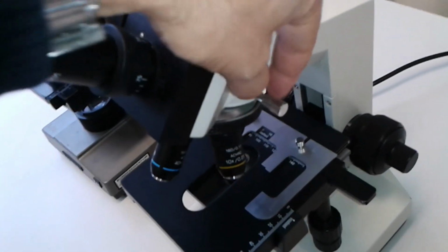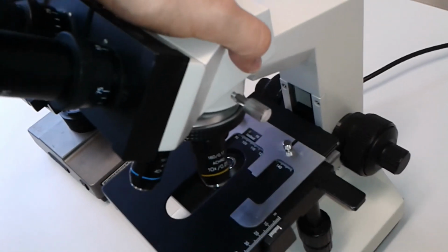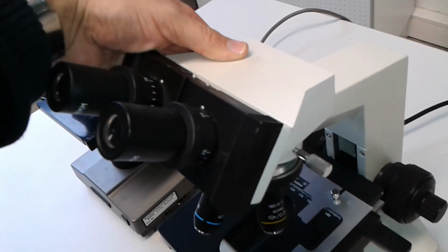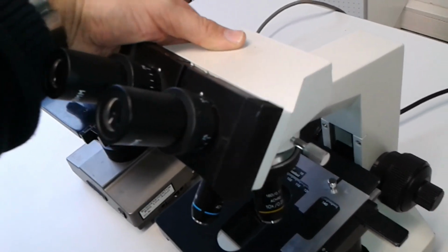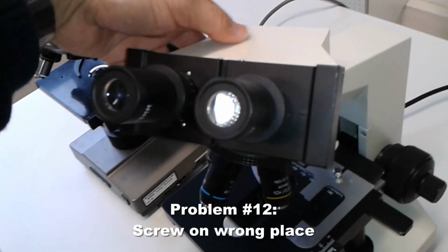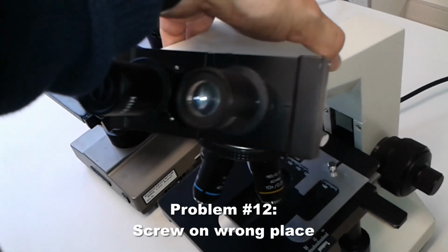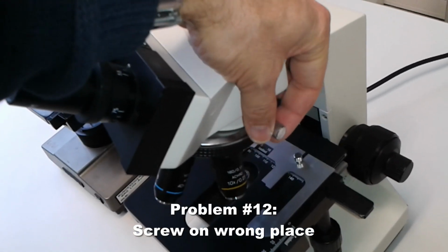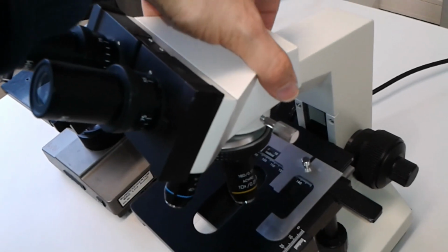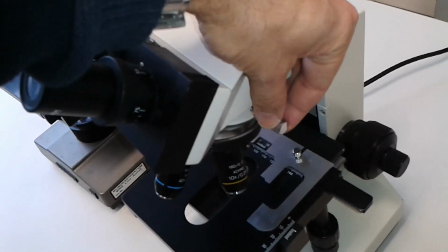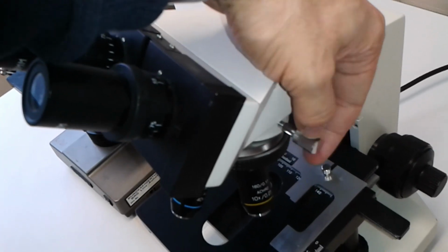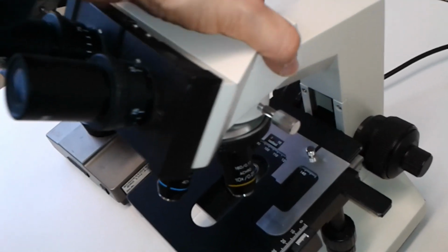And this is, I think, one of the worst problems of the microscope, and in my view a severe design problem. And that is that the microscope head, the binocular head, could not be attached properly to the microscope body. And the reason is the following: the screw that is holding the head in place was located in the wrong place. It was mounted too low.